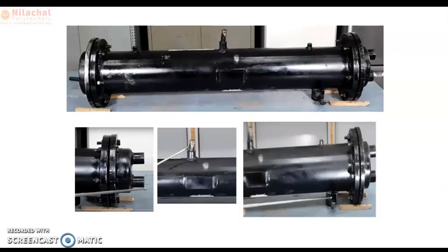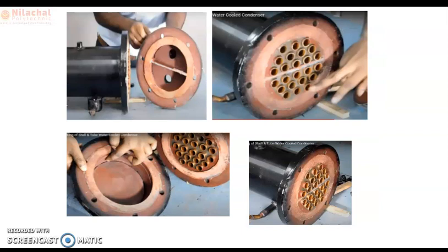However, if the maximum storage capacity for the liquid refrigerant is less than the total charge of the system, then a receiver of adequate capacity is added, in case a pump down facility is to be provided in the ice plant or the cold storage.